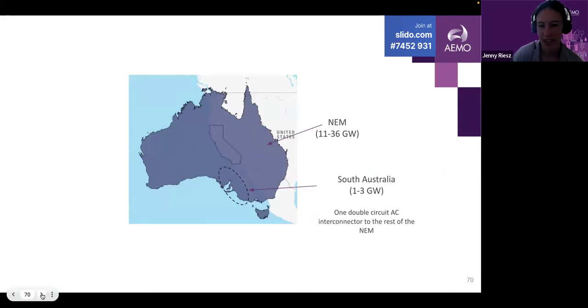To give you context for scale, here's Australia overlaid on the United States, with California shown. I'll focus on the South Australian region, circled at the bottom. That region is similar in geographic scale to California but has a much smaller electrical load, ranging between about 1 to 3 gigawatts. It's connected synchronously to the rest of the national electricity market, but only weakly through one double-circuit AC interconnector. That interconnector can experience unplanned outages, historically about once a year, requiring South Australia to operate as an island synchronously on its own.